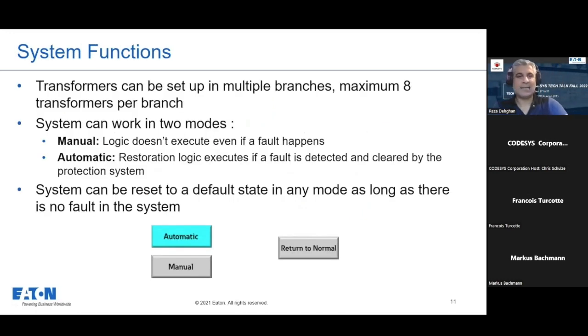Yeah, the system function. They were asking for a few different requirements for this code. First of all, the transformers can be set up in multiple branches, maximum 8 transformers per branch. The system can work in 2 different modes. In manual mode, logic doesn't execute even if a fault happens. On the automatic side, if something happens, basically it will start looking around to see what would be the best configuration of the switches, and it will do the restoration.